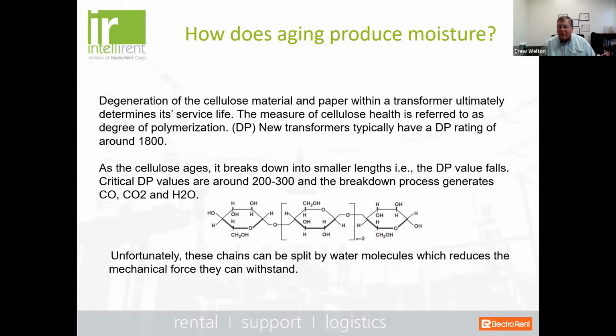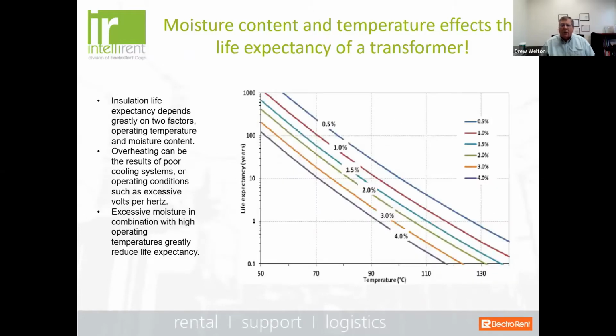Even if you never expose the insulating fluids to outside air, just the natural aging of the insulation will create moisture. Okay, now, what are the effects of moisture content? Well, the insulation life expectancy depends on two factors: operating temperature and moisture content. You can see that in this graph right here. On this bottom axis, we have the operating temperature and then the life expectancy. So there is the combination of the both.